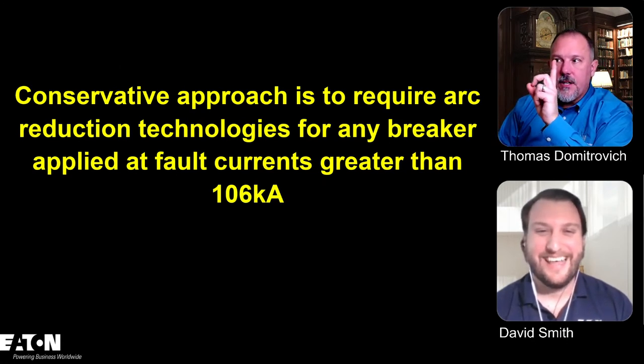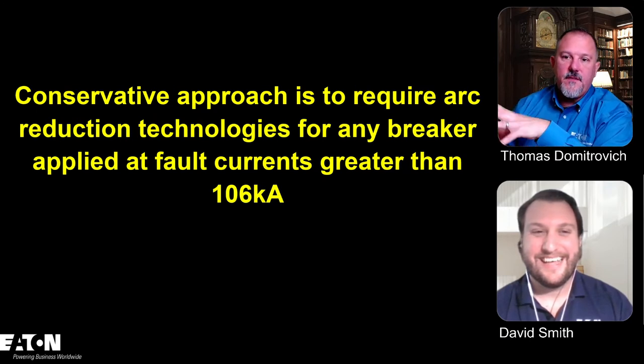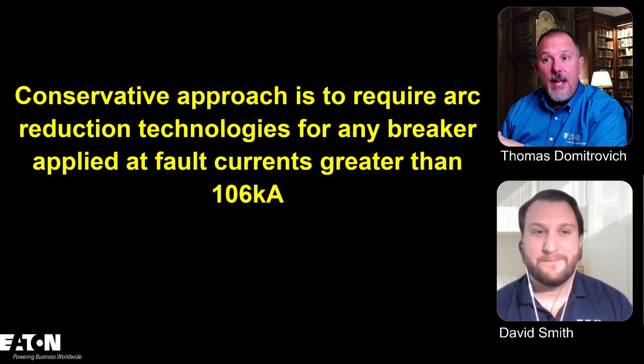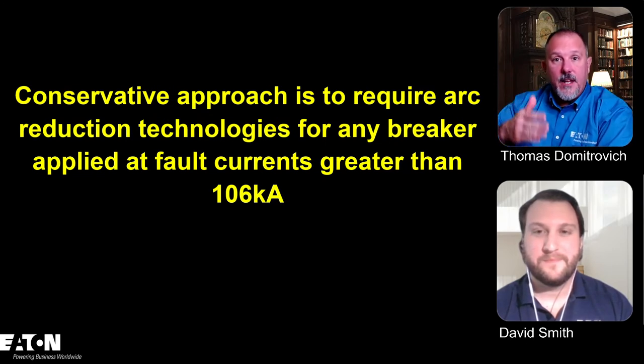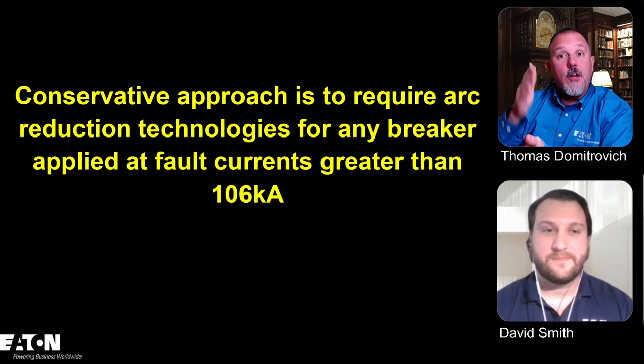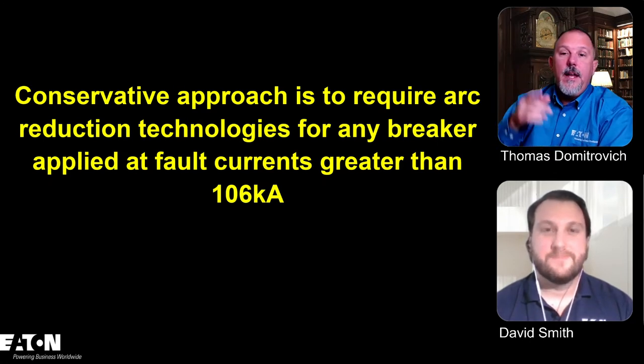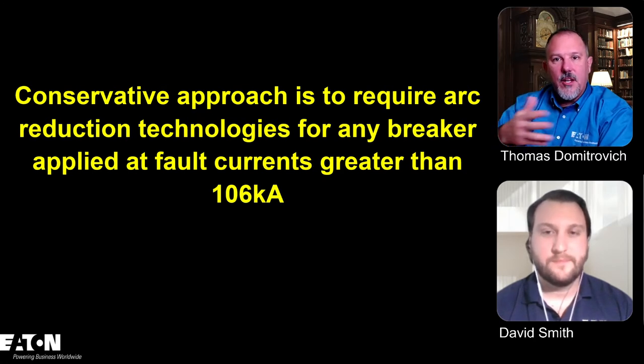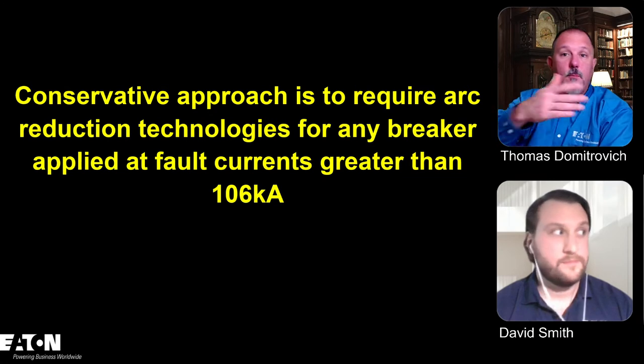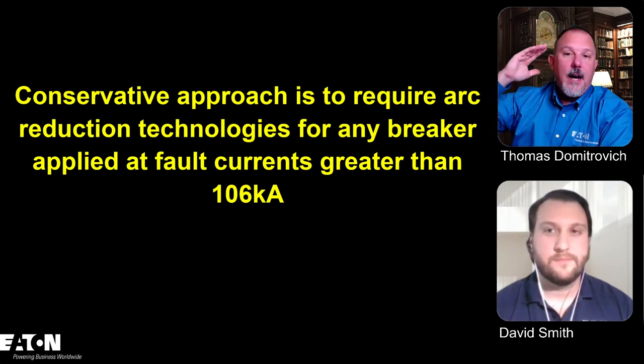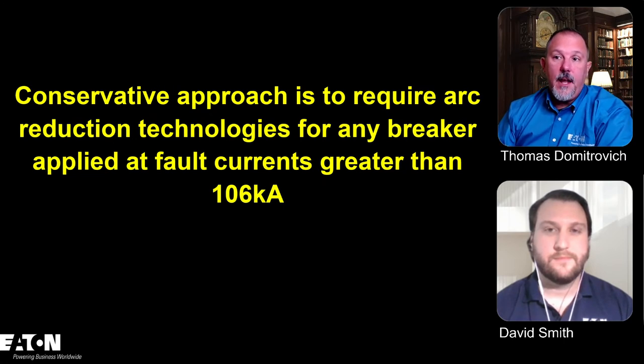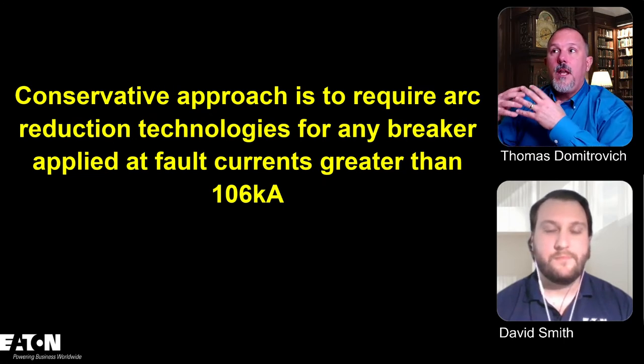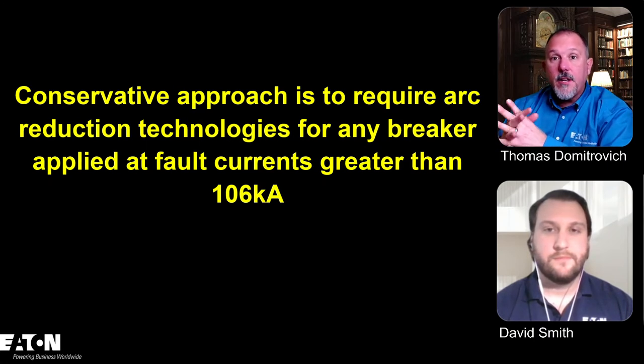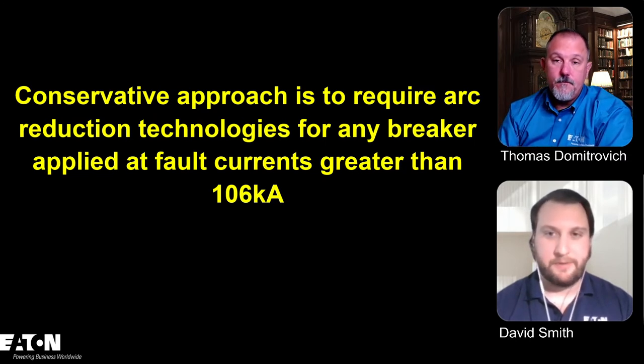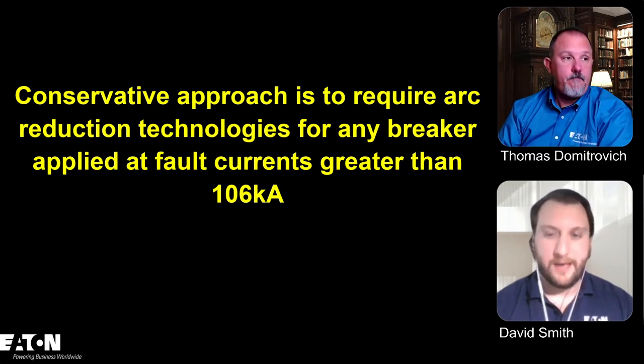So the conservative approach I take on all this: if I have available fault current greater than 106,000 amps, and I'm still not in the arcing, what I'll do is calculate the arcing currents at 106,000 amps. And if I don't actuate my equipment, my instantaneous on my circuit breaker, or if I'm not in the 0.07 second for 240.67, I am throwing on an arc reduction technology. And then you just want to make sure that you're in that technology's region at the arcing current values of 106,000 amps. Right. Make sure it's calibrated and set to everything. Right. You can't just slap it on. Make sure you do everything, set it to where it needs to be, and then you should be good to go.